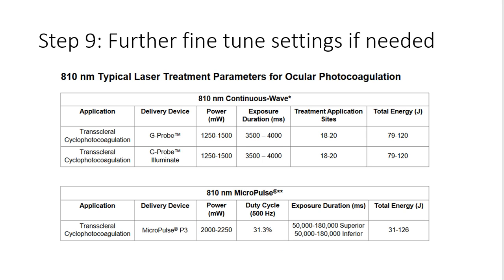Here's a chart of the different laser settings that you can use for the CPC versus the micropulse. In general, for the CPC, it's okay to hear pops on some of your applications, but you don't want to hear a pop on every application. So if you're hearing a pop on every application, then you want to turn the power down. If you're not hearing any pops, then you may want to turn the power up.